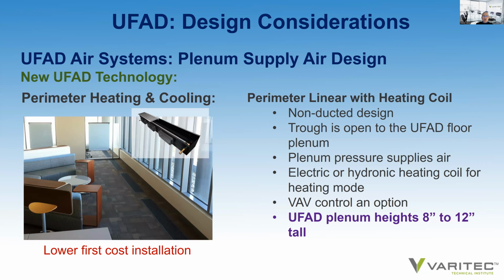For perimeter zones, we now use plenum trough diffusers that have a damper at the inlet that will adjust, either as a two-position damper that goes open or closed, or it can actually vary in a VAV system in cooling mode. And this diffuser comes with a heating element inside. You can either use an electric coil or a hydronic coil to provide perimeter heating during our colder winter months. But in the summer, it will have a VAV characteristic where the damper that allows air from the plenum into the trough itself modulates, thereby regulating airflow to maintain thermal comfort at the perimeters.